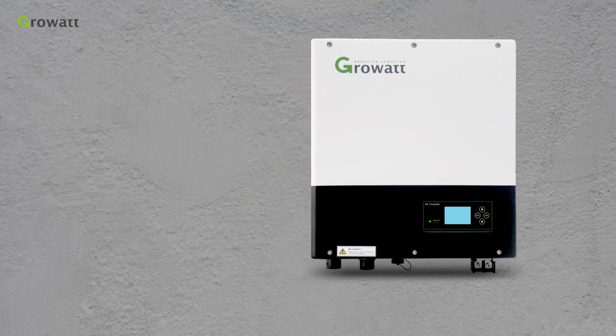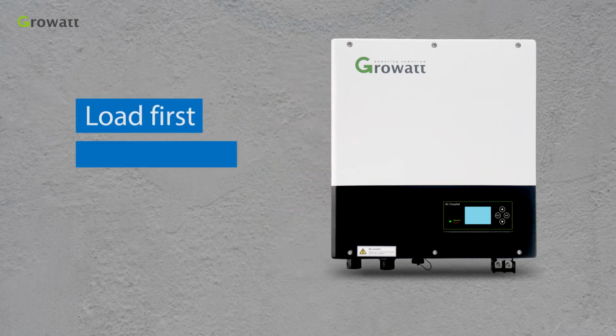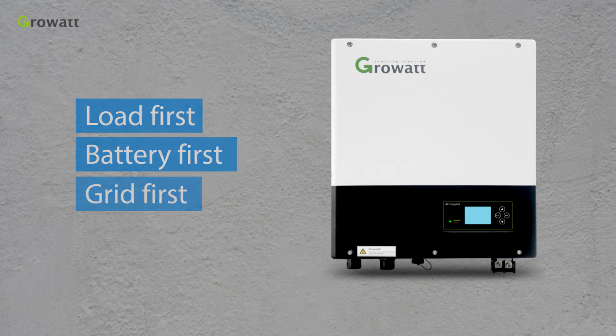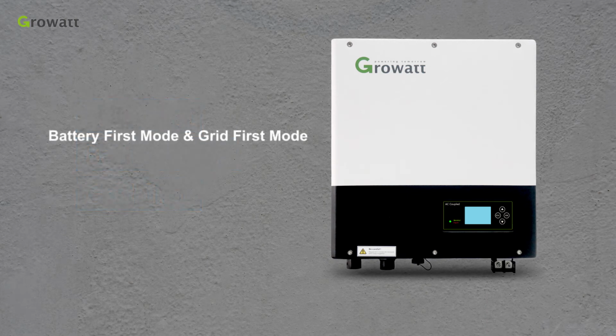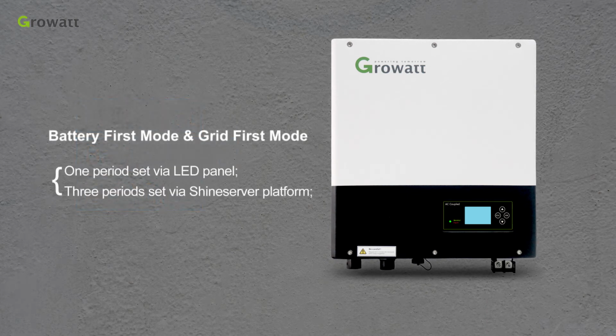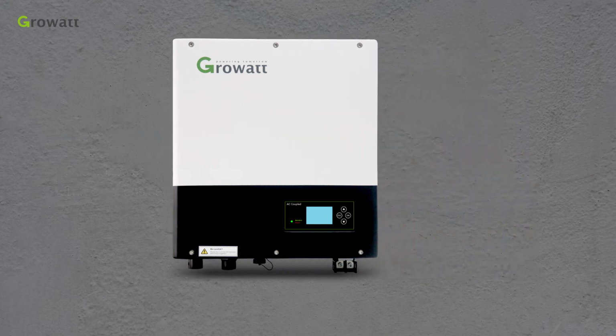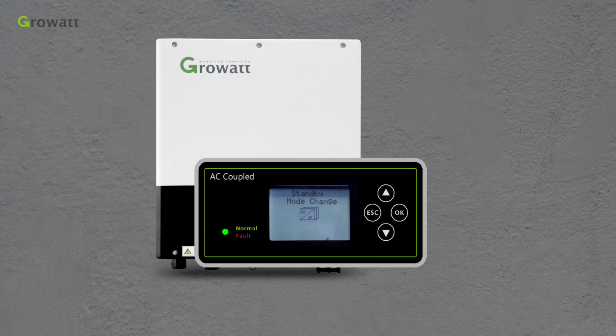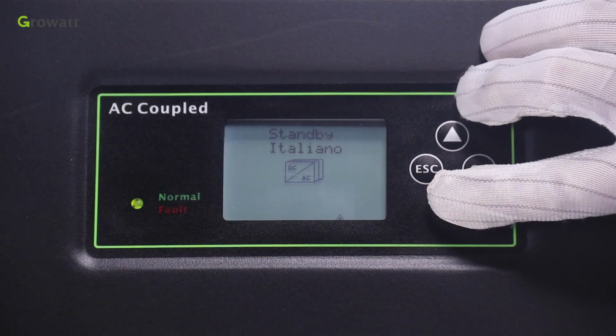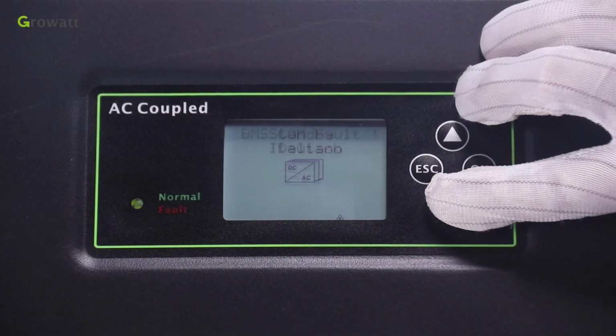SPA can be used in different modes: load first, battery first, and grid first. For battery first and grid first modes, the customer can set the timetable. Through the LCD, one time period can be set. Through the Growatt Shine Server, 3 time periods each can be set. From the LCD panel, we can change the mode manually, also including language, system time, lead-acid cells charging voltage, default is 58 volts, discharge low voltage and so on.